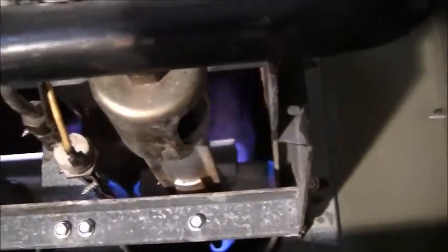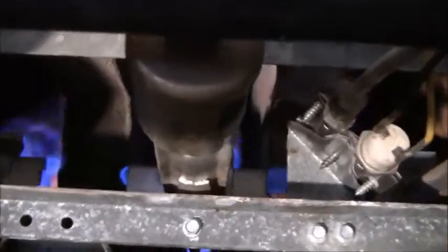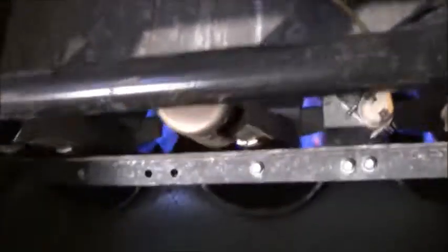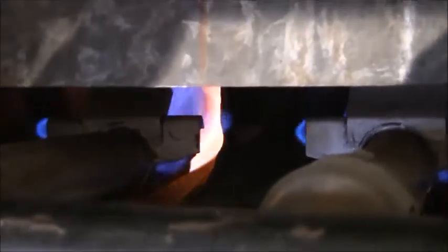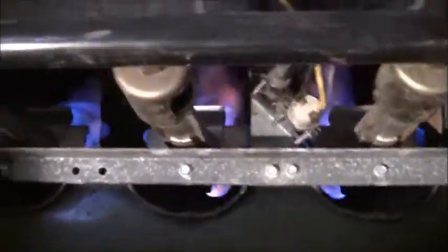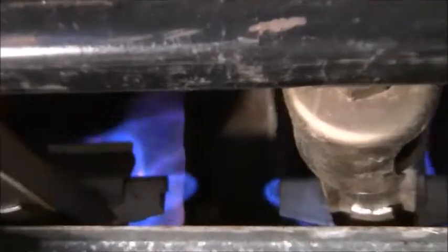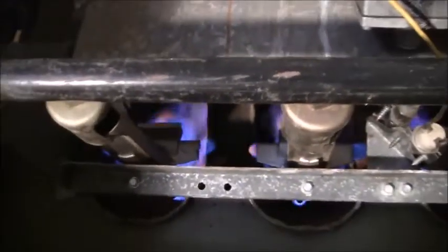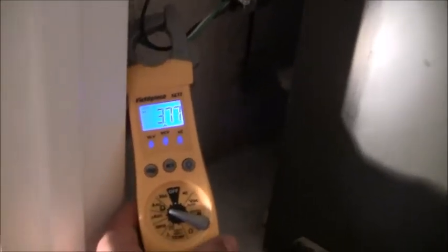So we have to give it a couple minutes. It's going to take a few minutes for the fan to come on. Mind you, this is a 40-year-old furnace. Maybe that's just what the burners look like on a 40-year-old furnace. And the newer furnaces, they look a lot nicer. You can see some coloring going on right there. Oh, here we go. The fan is kicking on. We can check the amp draw on the fan, which we did earlier. I think it was 3.83 earlier. So it's 3.8 amps, which is fine. So we're fine on the amps.